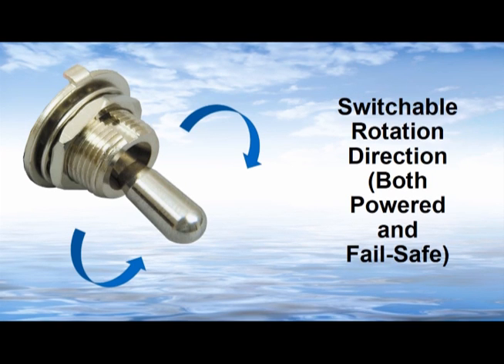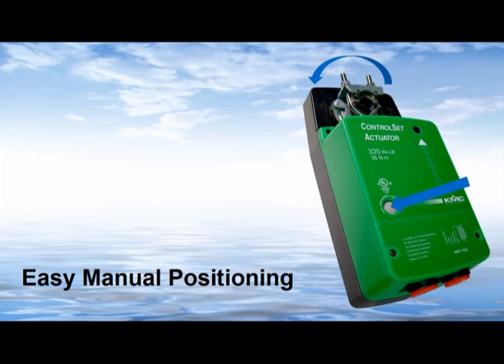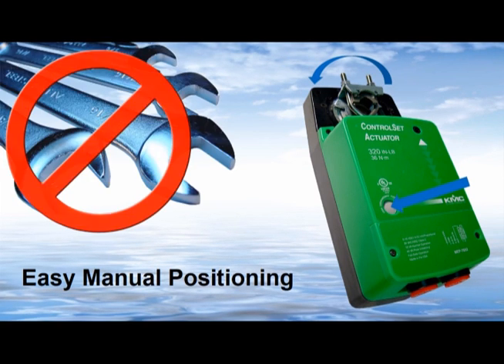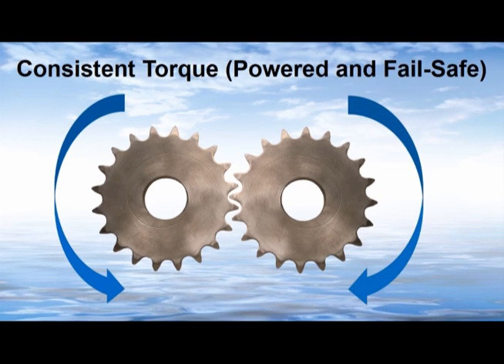Not only can a capacitor driven failsafe easily change directions, it might also be turned off if desired, such as for testing purposes. The easier installation of capacitor driven actuators is further enhanced by a quick release button or lever that allows easy manual positioning of the shaft. Spring returns, on the other hand, usually require a wrench to manually wind the shaft into position, if manual positioning is available at all. Spring returns typically drive much faster and with excessive torque during failsafe mode, potentially damaging equipment. But capacitor driven actuators provide consistent torque during failsafe as well as powered modes.